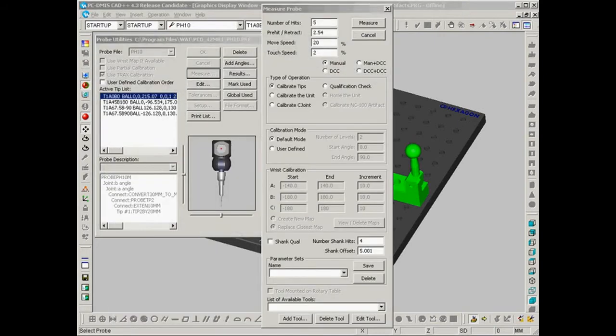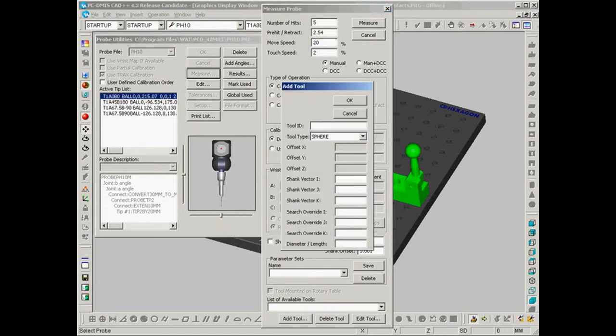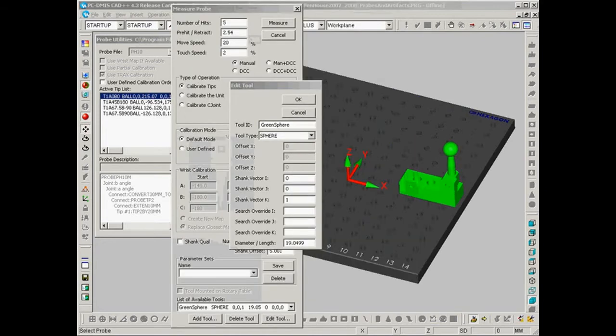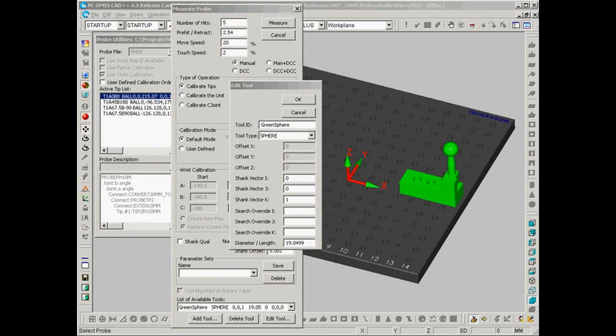The next thing we need to do is add a hardware profile that describes this tooling ball. So under measure probe we're going to select add tool and build up the profile for each of these calibration tools. It's important that you get the calibration artifact's vector correctly inside of the edit tool dialog. You'll notice this green sphere points in the Z plus direction, so I've input a vector of 0, 0 and 1, and then down here I've added its size.